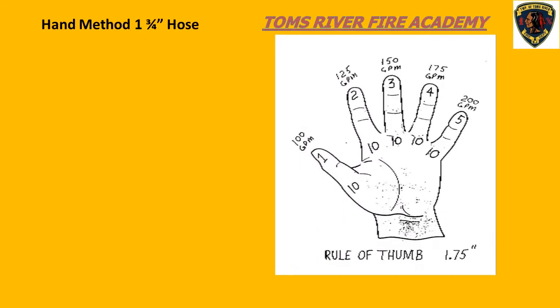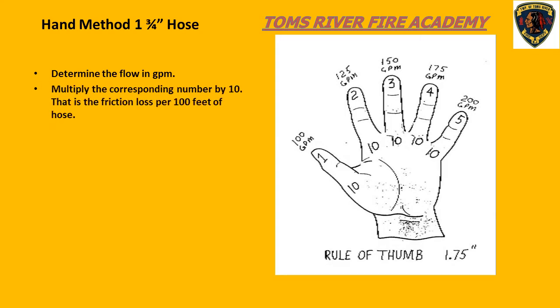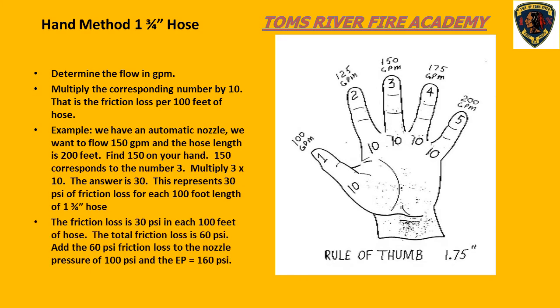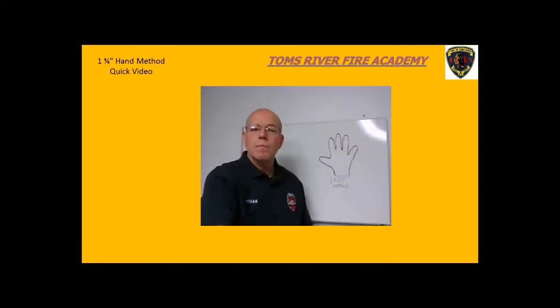Here is the hand method rule of thumb that we can use to determine friction loss. The first thing we always need to know is the required flow in gallons per minute. Each finger has a designated flow in GPM, and each flow also has a designated number. To find the friction loss, just select the flow, take the assigned number, and multiply it by 10. That will give you the friction loss for each 100-foot section of hose. The next slide has a short video to walk you through the hand method for inch and three-quarter hose.